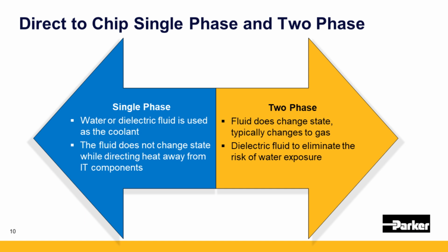In addition, you can have this as a single phase or two-phase setup. Single phase - water or some water glycol mixture - is typically one of the best choices since it has a fairly high heat capacity. With not too much delta T temperature rise, you're able to capture a significant amount of heat generated off those GPUs and CPUs. The fluid doesn't change state as it goes across, making it much simpler - one type of fluid processed all the way through.